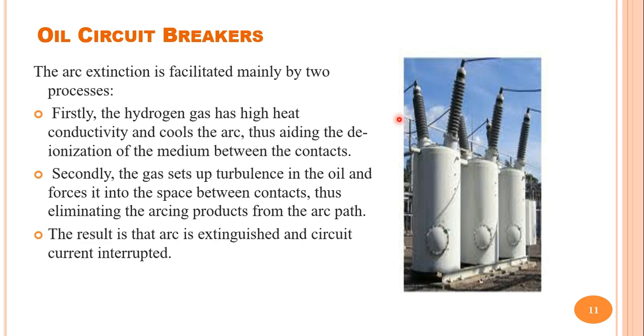Another factor which facilitates arc extinction is that the gas sets up a turbulent flow in the oil. It forces oil into the space between the contacts and ionized particles between the contacts are swept away from the arc path. By using these two properties, the arc can be extinguished.